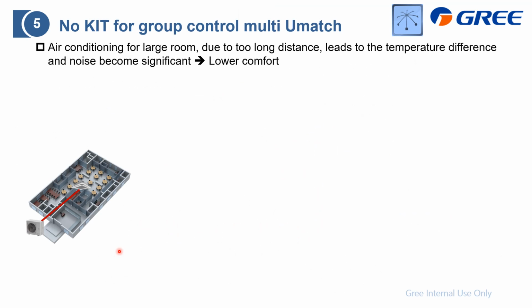For the big capacity UMatch, there is always a problem, which in these pictures you can find. This is the cassette type, for example 14 or even 16 kilowatt. For the capacity, for this room it is okay, it's quite enough. However, that relates to this room, which is close to this indoor unit. Of course it will cool down, but far away from it, it will still be warm or even hot, which means the temperature is uneven. To make the temperature even, we need to raise the indoor fan RPM, right? And higher indoor fan RPM also leads to big noise.